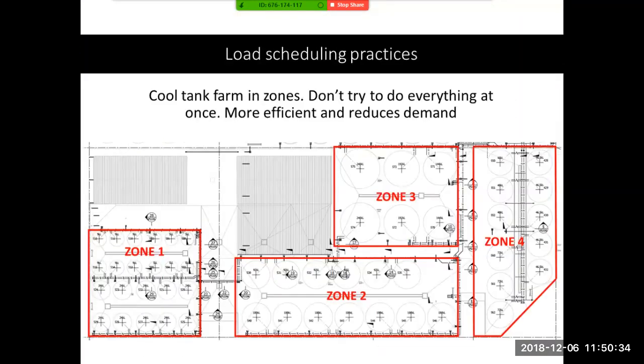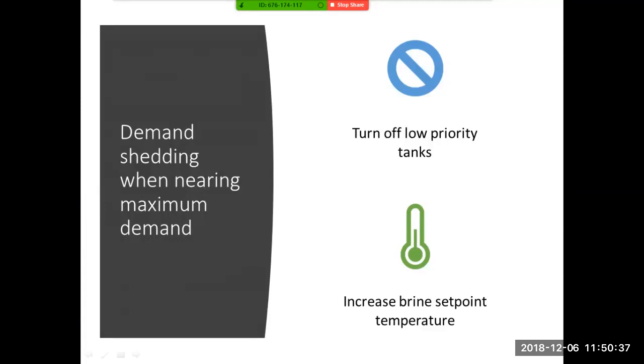But there are two ways that you can do this. Again, we're looking at refrigeration because it's the biggest energy user. So when you're nearing that peak in demand, you can turn off your low priority tanks, which will cut your refrigeration loading, and you can also increase the brine set point temperature of your fridge system. Basically that cuts the chiller out, which gives you heaps of capacity left to play with, so you can make sure you can do all the other processing that you need in your winery.